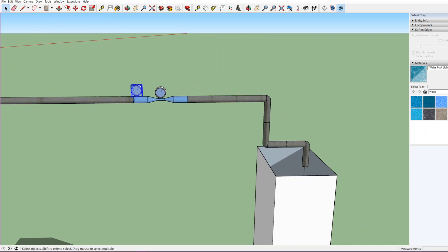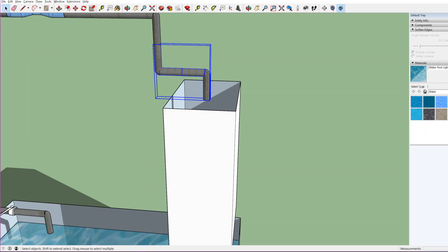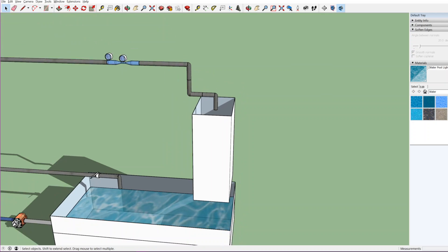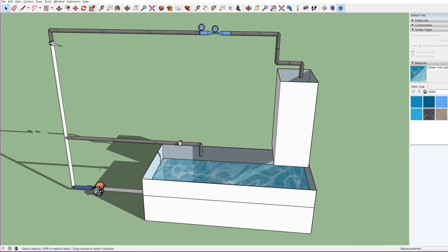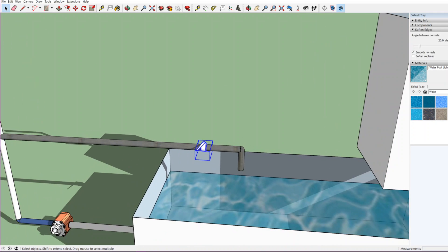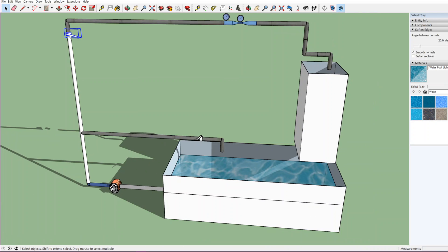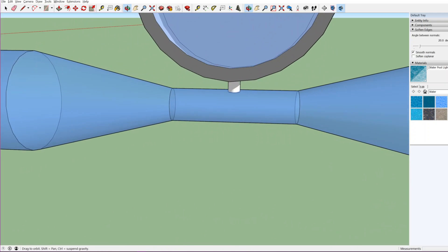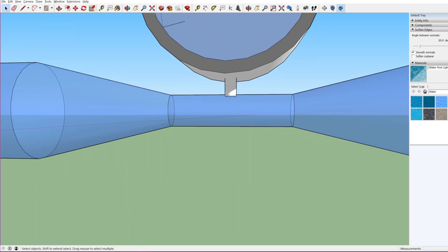The water then goes back to the reservoir. If required, we can measure the discharge in the discharge measuring tank. We can control the flow by operating this valve or this valve. When the flow is very high, the velocity at the throat will be very high, and we may observe cavitation at a certain value of discharge.